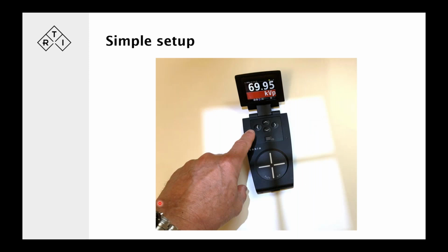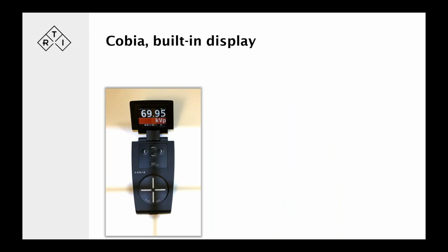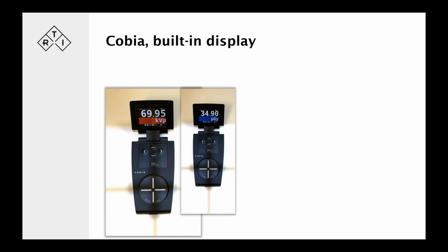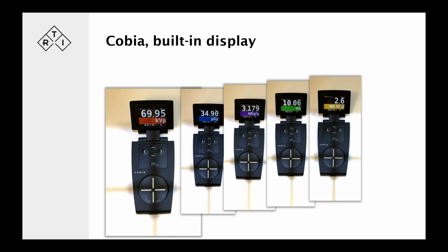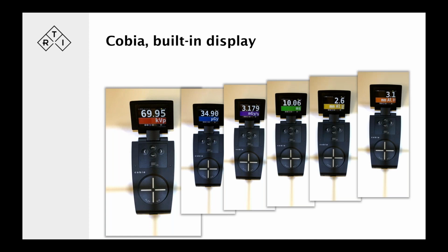So it has its built-in display, and it's a very easy setup. Just place it in the beam. I just have my hand in there for scale. Set it up for whatever you need, power it on, and it comes on default with the standard measurements. The built-in display gives you normally the kVp, and as default, it will then scroll after an exposure to show you the dose. If you want it in gray or Röntgen, you need to set that up in the user settings. Dose rate, exposure time, HVL, and total filtration. So these values will scroll through the display.